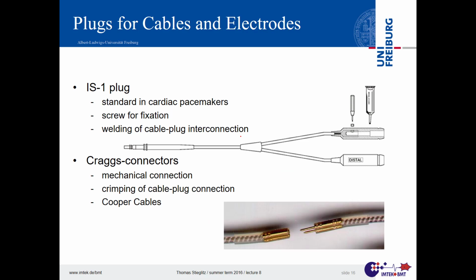And if we have a feed-through, that does not mean that we already have something connected, so we would need cables and connectors to that. And most of those cables and connectors are derived from the pacemaker industry. We already have those cardiac pacemakers here, so we don't need too many contacts there. That's the beauty. And therefore, cables and connectors could be relatively simple. But it's limiting in the number of wires.